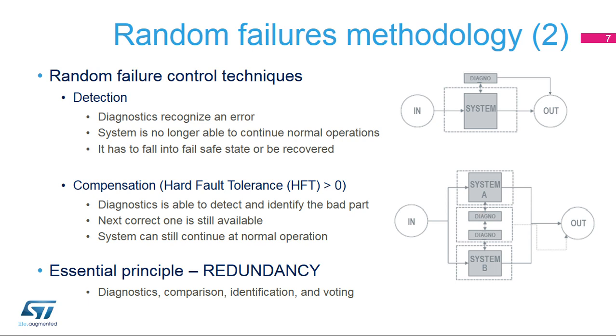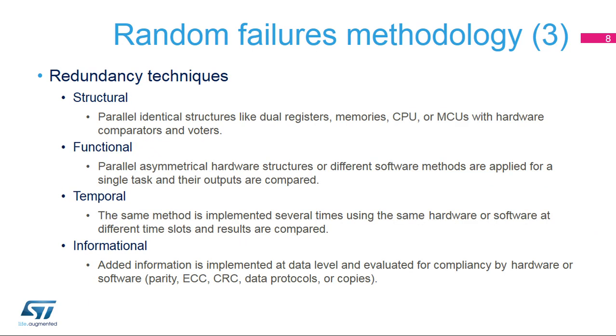Standards recognize hard fault tolerance, or the maximum number of errors which a system can absorb while it can still continue at normal operation. In addition to specific functional testing, redundancy is the essential diagnostic principle. Both detection and compensation techniques always require a sure level of redundancy to be efficient. Compensation is considerably more demanding than detection, as not only discrepancies but the correct state has to be identified as well. To do so, specific comparison and voting mechanisms have to be additionally applied.